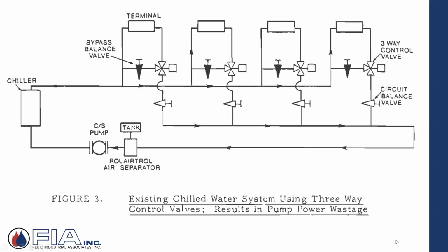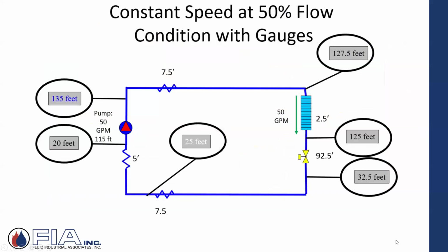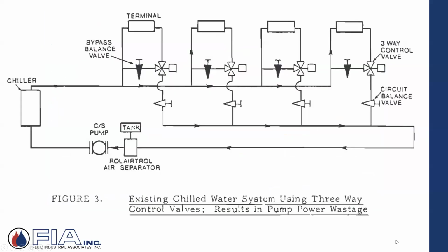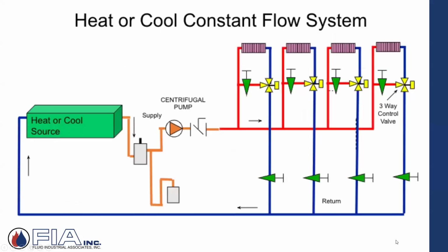Now, it would take away some of the issues that you experience with this 2-way control valve, seeing this really excessive buildup in pressure. But as it states here, waste of energy. You might not see it so much today, because at some point ASHRAE, I think it's ASHRAE 90.1, which is X number of years old, was really saying this is such a waste of energy. We want you to plug that bypass port. If you're not going to take the valve out and make it a 2-way, as they introduced variable speed, they wanted you to at least plug that bypass port. But anyways, that's a modern version of that same older drawing.